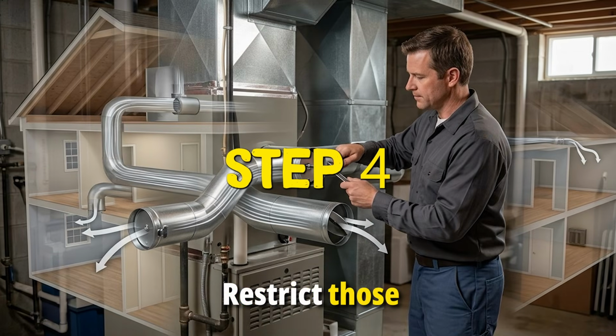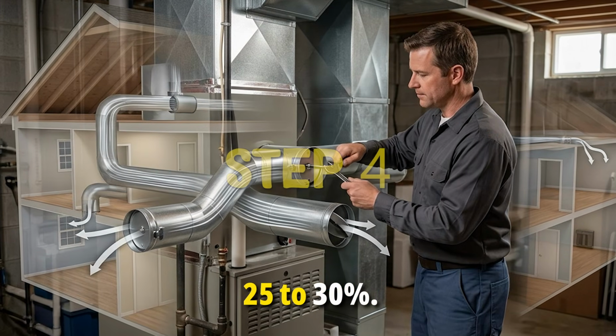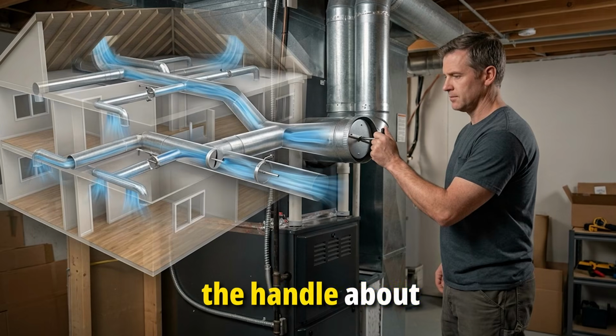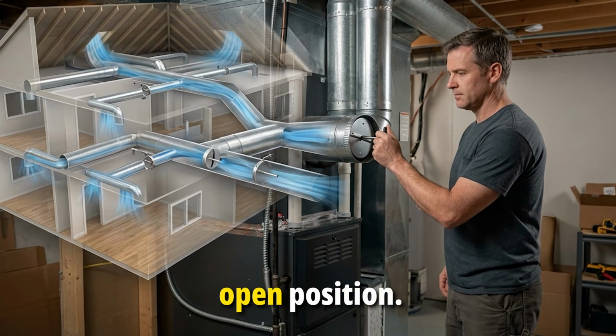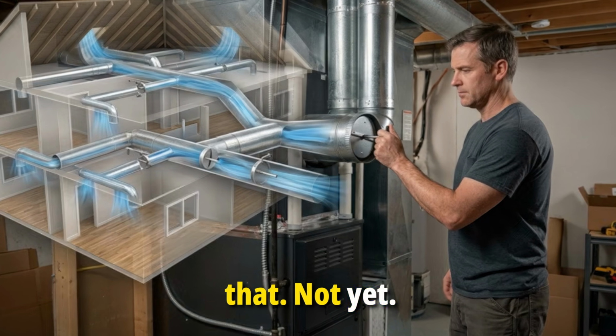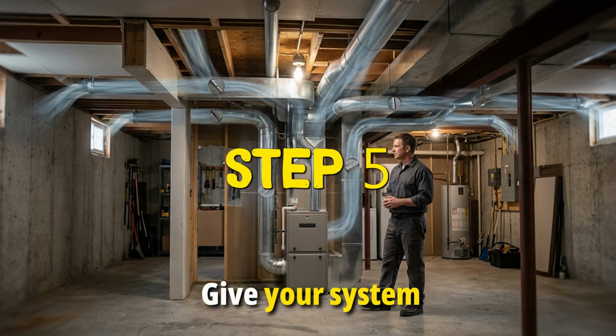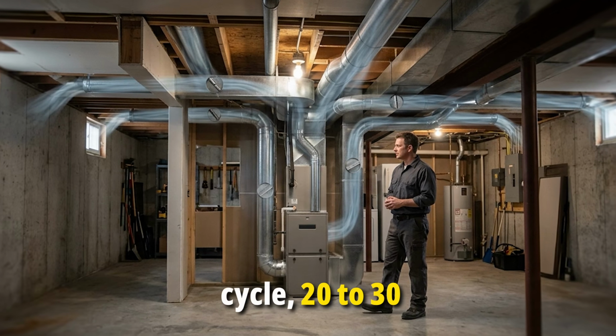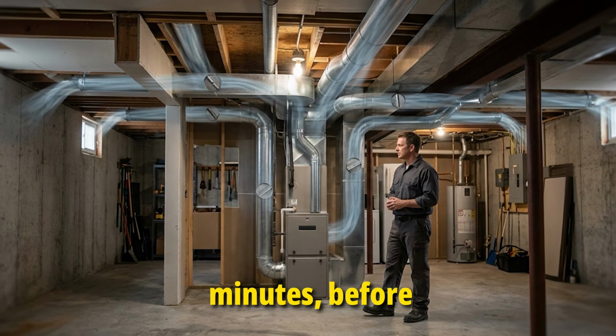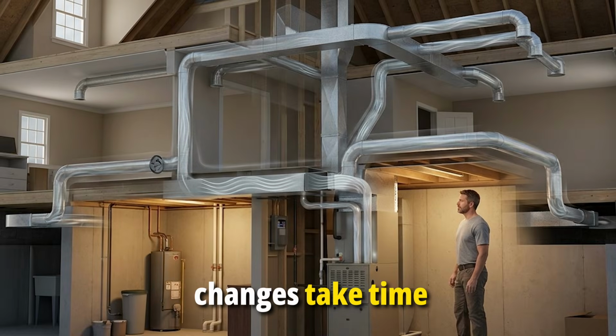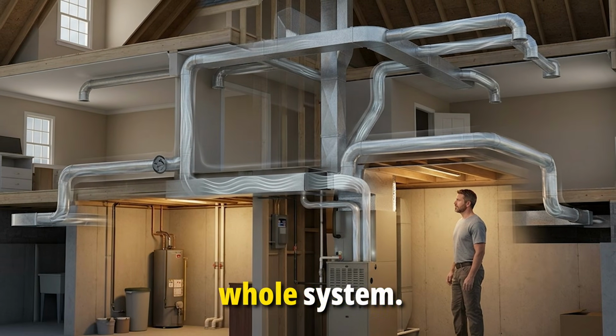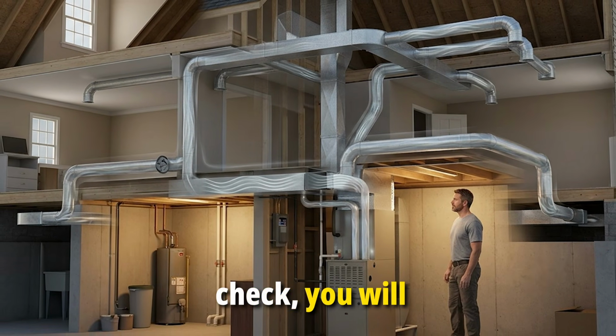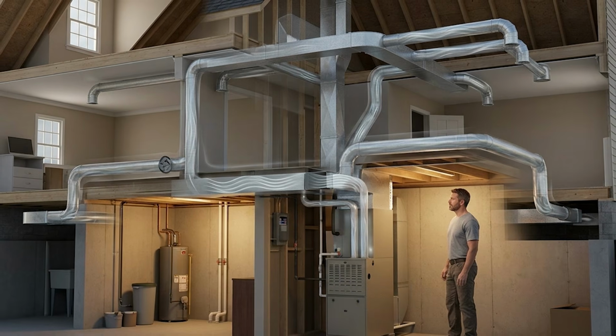Step 4. Restrict those dampers by about 25 to 30%. Rotate the handle about a quarter turn from the fully open position. Not more than that. Not yet. Step 5. Wait. Give your system at least one full cycle, 20 to 30 minutes, before you measure again. Pressure changes take time to propagate through the whole system. If you adjust and immediately check, you will not see the real result.